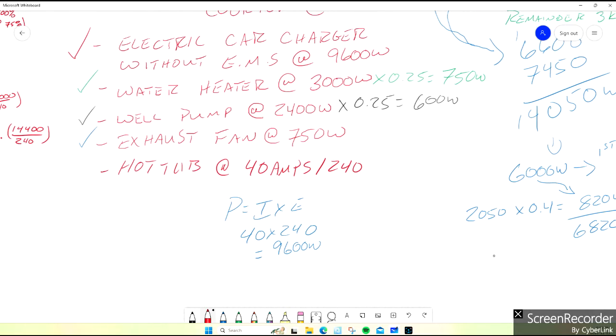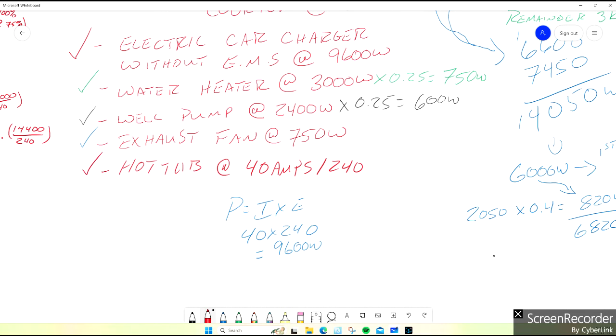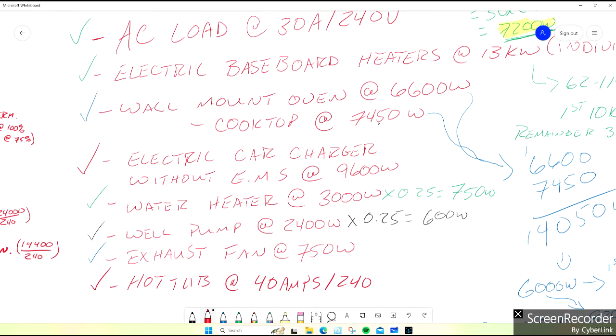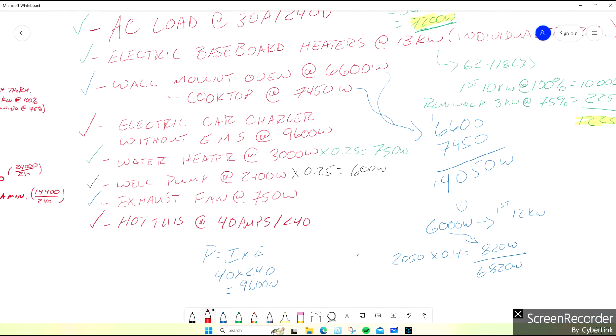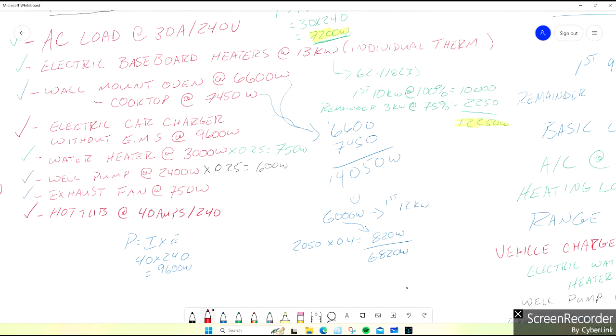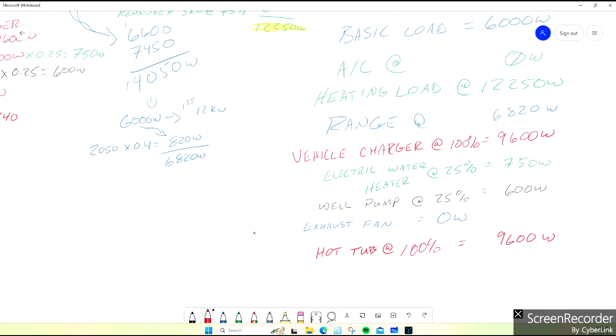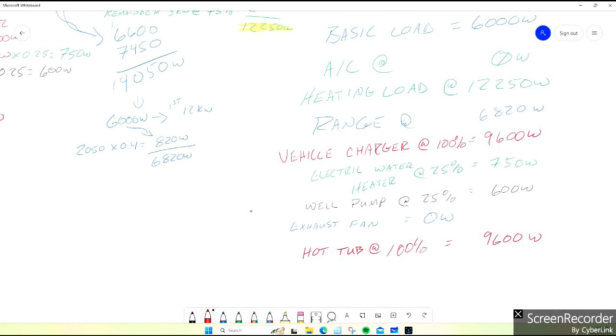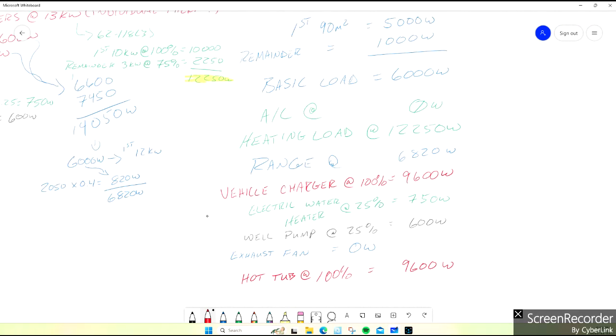We have taken care of all the items in this home. So we're done our list. We did our basic load. We came through and took care of everything that's going in the home. I should mention too, if you're wiring homes, especially custom homes, always talk to your client and make sure you understand fully what is going in that home, so you know how to properly size the service. Here, this is what we had. So all you do now is add up all the loads that we came up with.